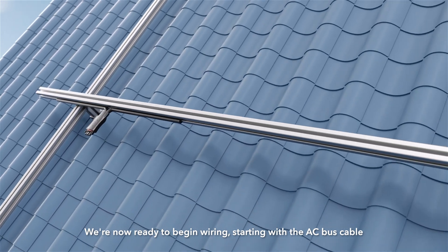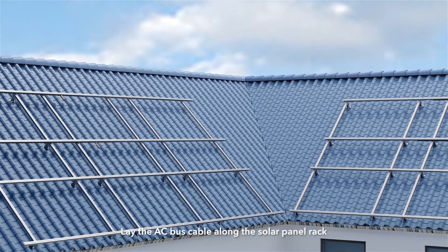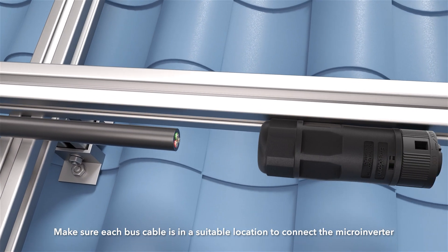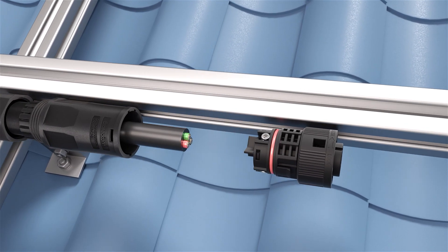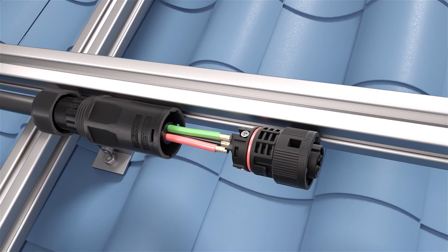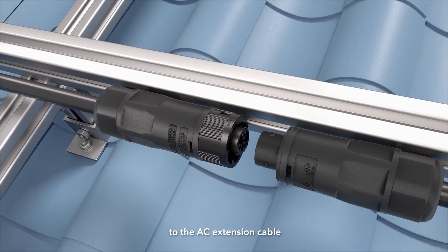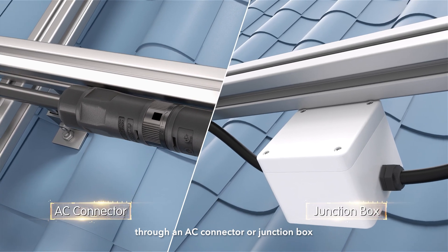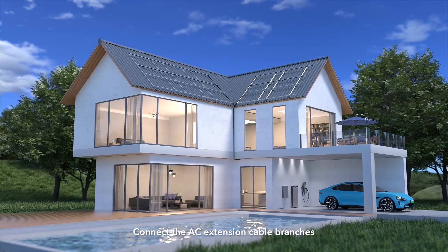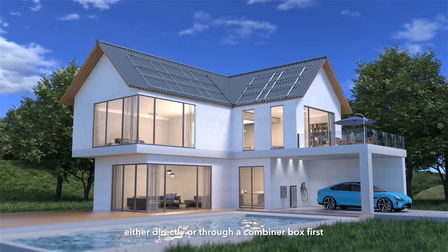We're now ready to begin wiring, starting with the AC bus cable. Lay the AC bus cable along the solar panel rack, making sure each bus cable is in a suitable location to connect the Micro Inverter. Connect one end of the AC bus cable to the AC extension cable through an AC connector or junction box. Connect the AC extension cable branches to the Anker SOLIX X1 Backup Controller, either directly or through a combiner box first.